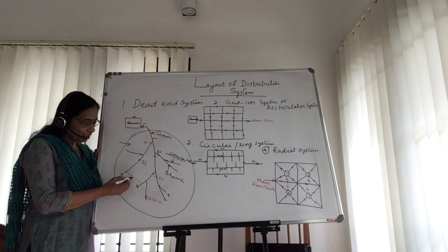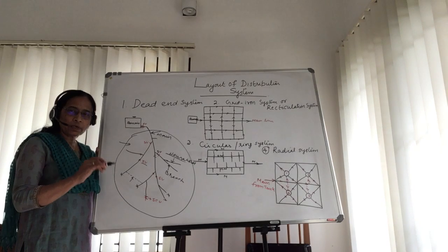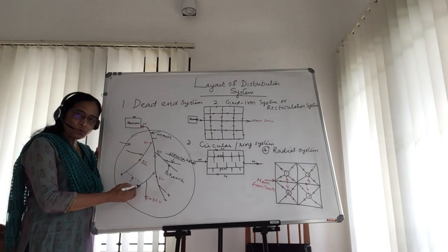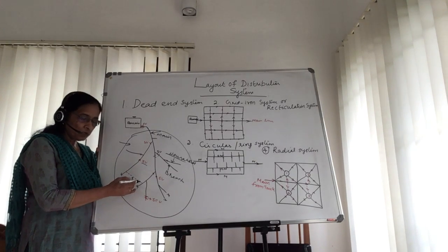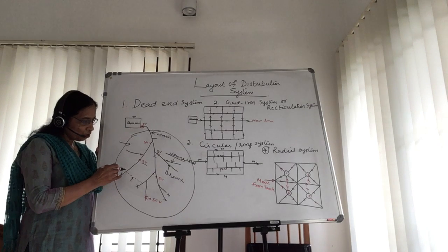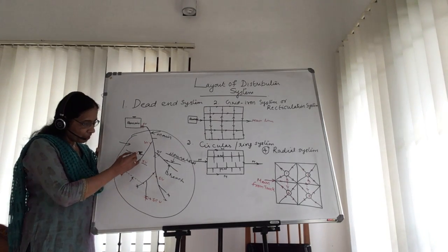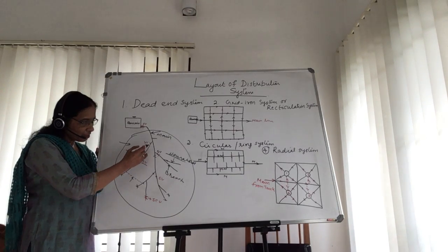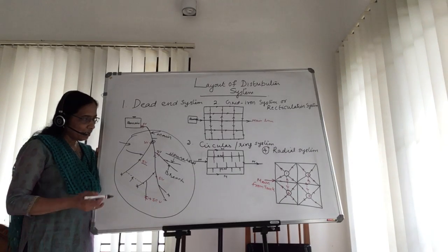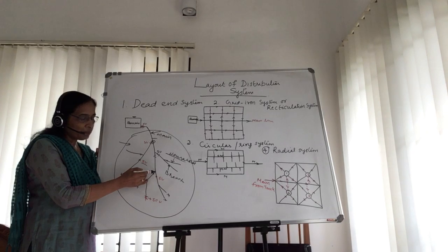This dotted line, you can have an interconnection between these two lines if you want to increase the supply or if you want to increase the pressure at these particular points. So imagine that in this line you are getting a very low pressure, whereas here this branch is starting from the main line. This line is starting from the main line before or ahead of this branch line.